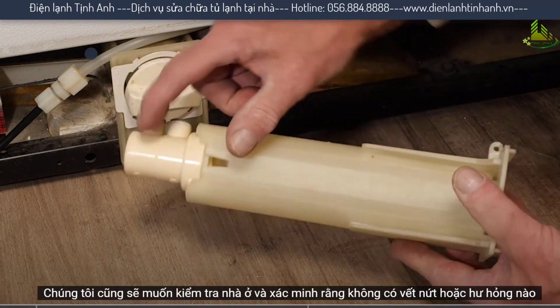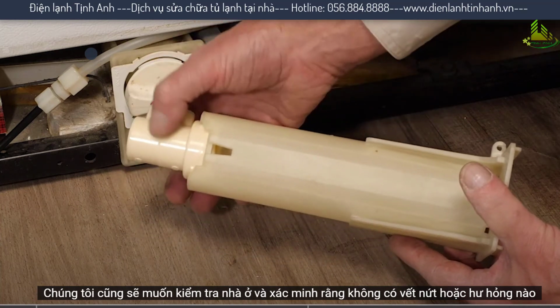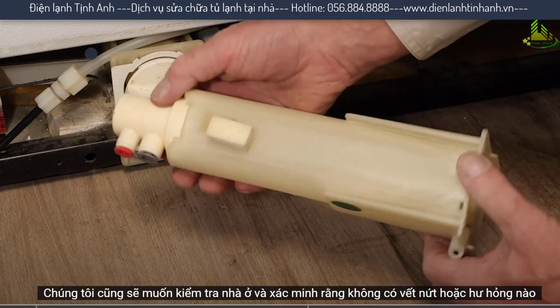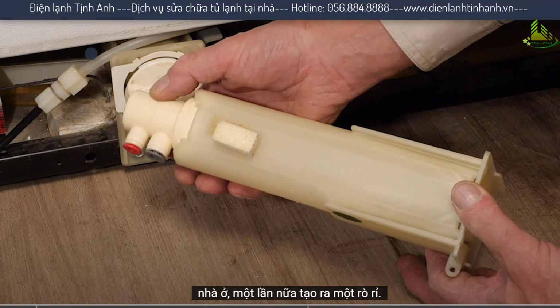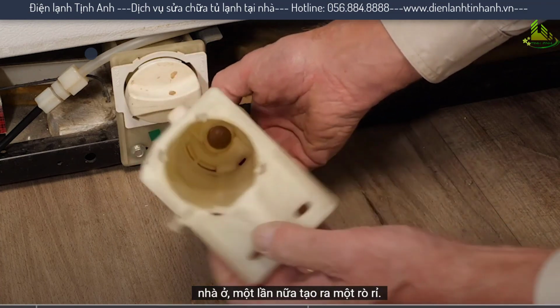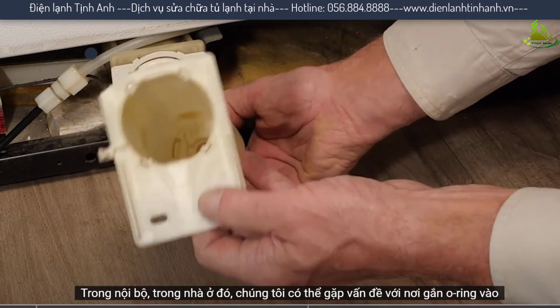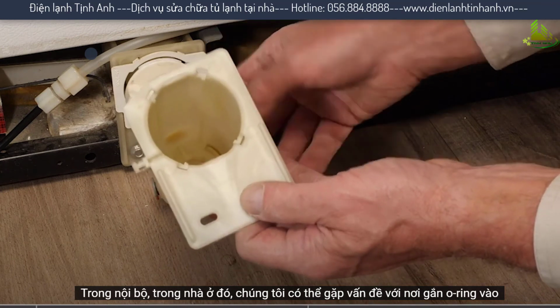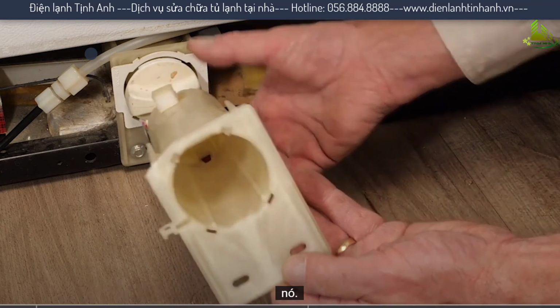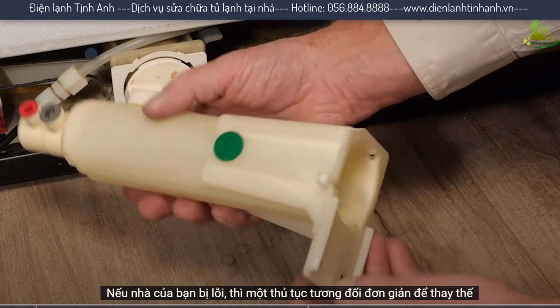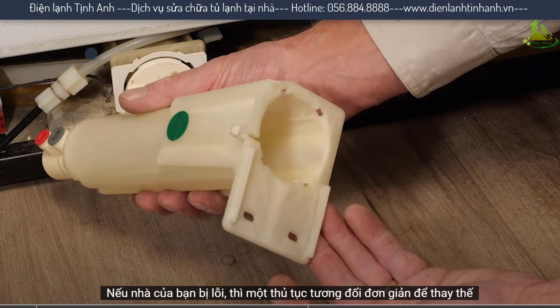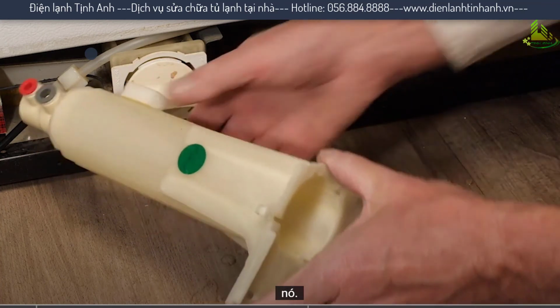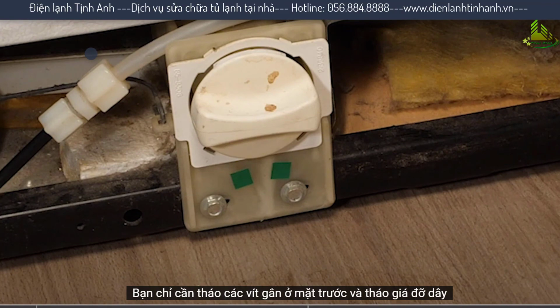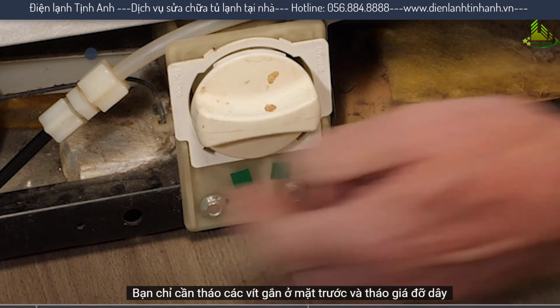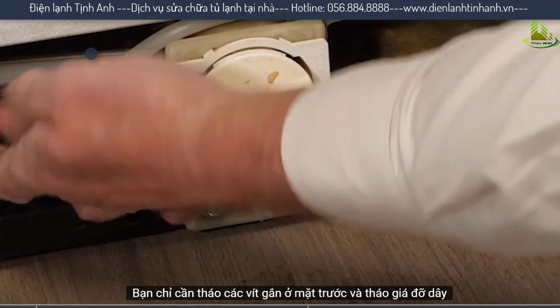We'll also want to check the housing and verify that there are no cracks or damage to that housing, again creating a leak. Internally in that housing, we may have an issue with where the O-rings attach to it. So if it turns out that your housing is at fault, it's a relatively simple procedure to replace it.